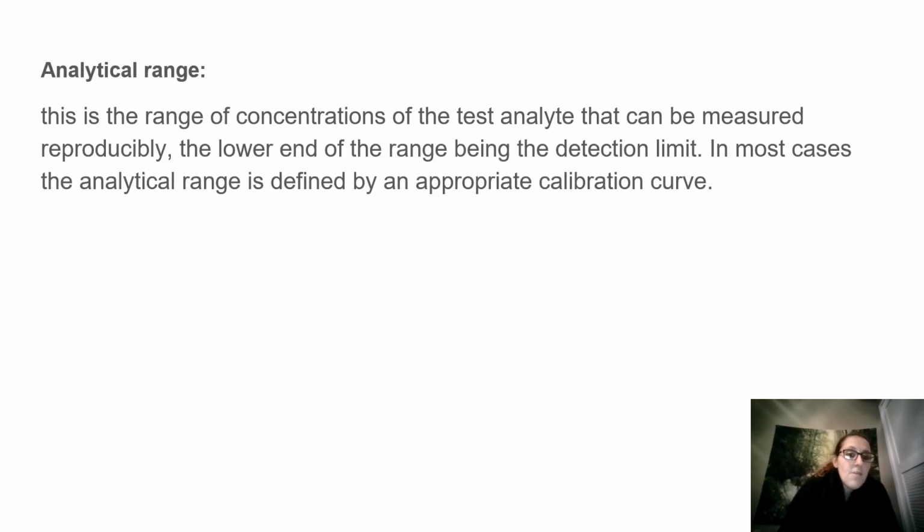Analytical range. This is the range of concentrations of the test analyte that can be measured reproducibly, the lower end of the range being the detection limit. In most cases, the analytical range is defined by an appropriate calibration curve.